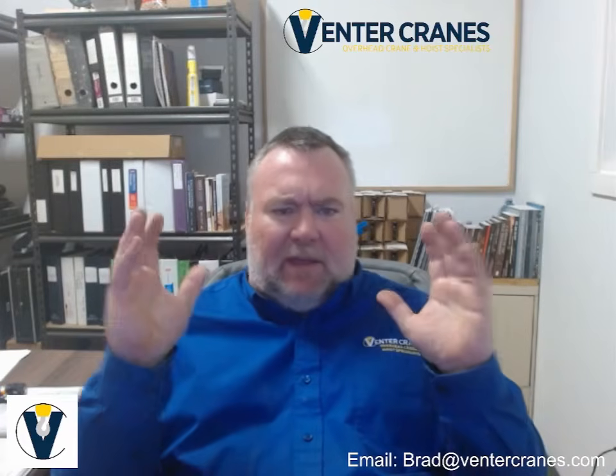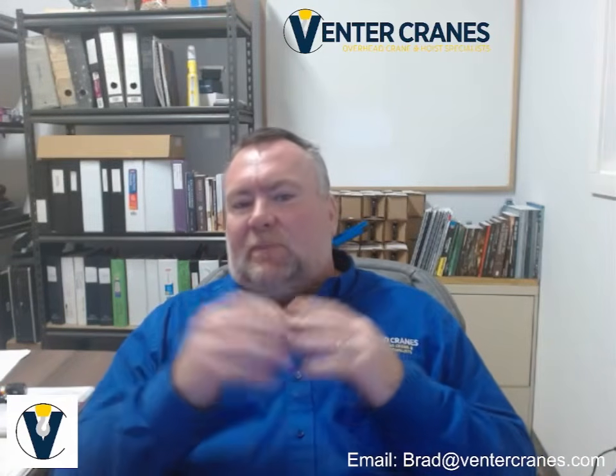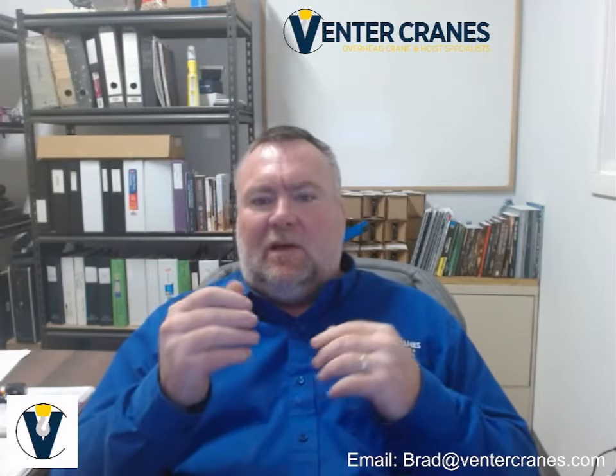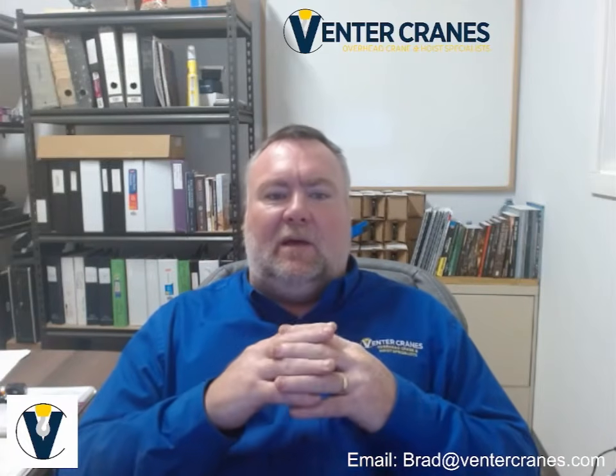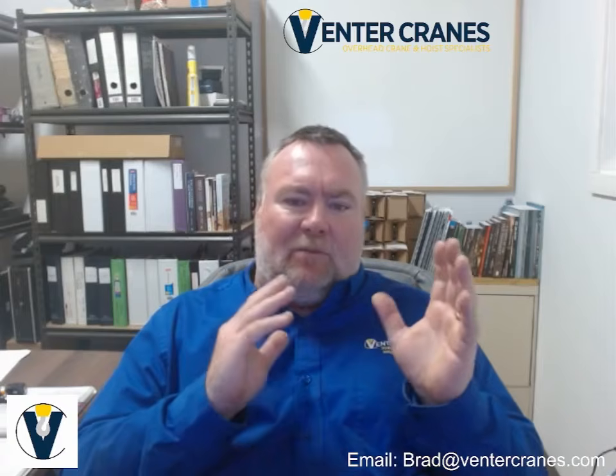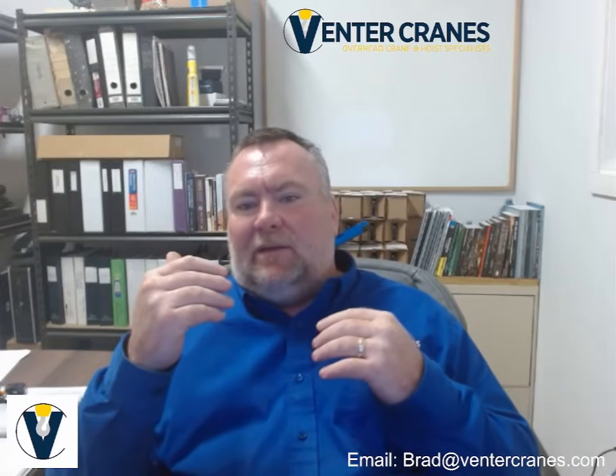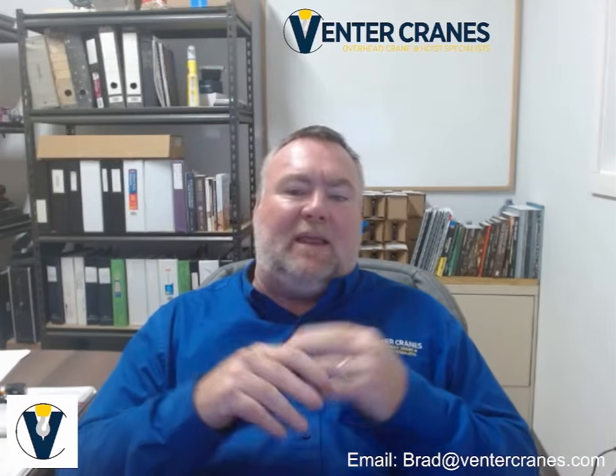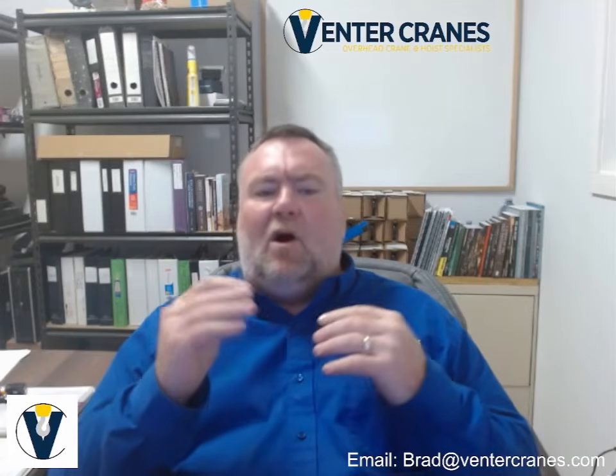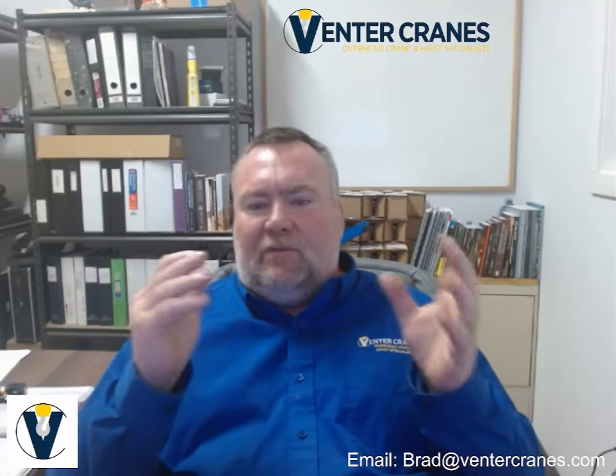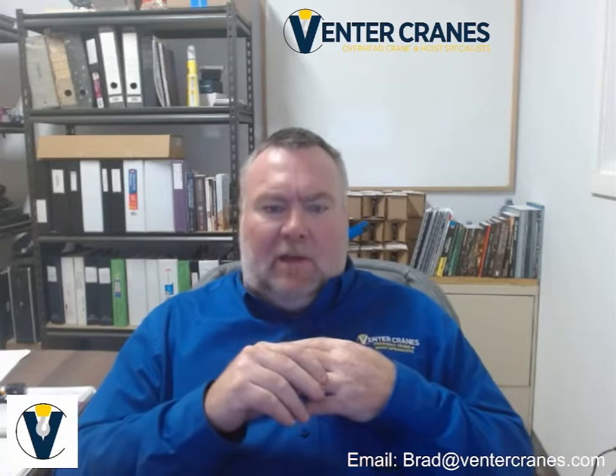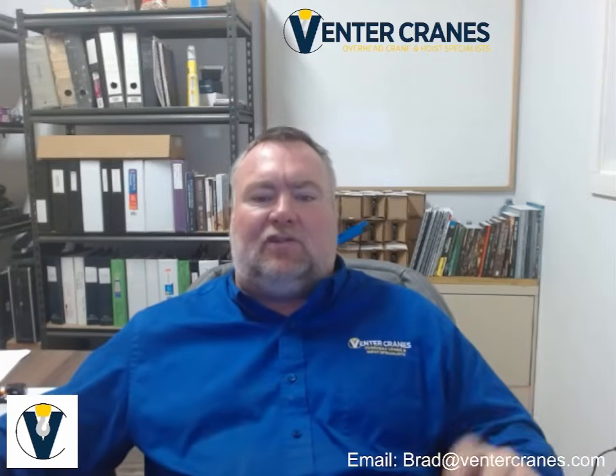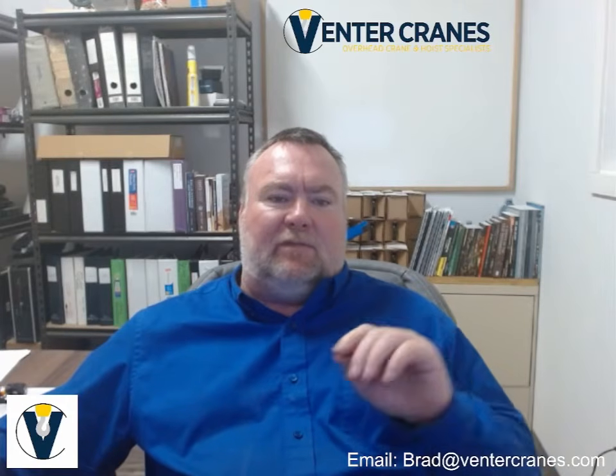So some key takeaways here. Operators must be trained, evaluated and competent before using any crane or hoist. Training includes theory and hands-on practice with records kept and should be retrained every 3 years, right? Employers are responsible for maintaining written procedures and training records. Operators must perform functional checks at every shift and follow OHS, CSA and manufacturer instructions. Competent operators are the foundation of crane safety, right?